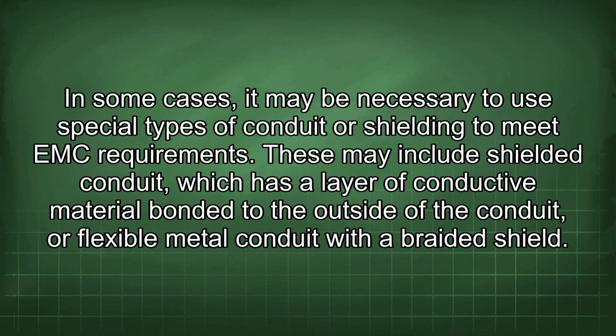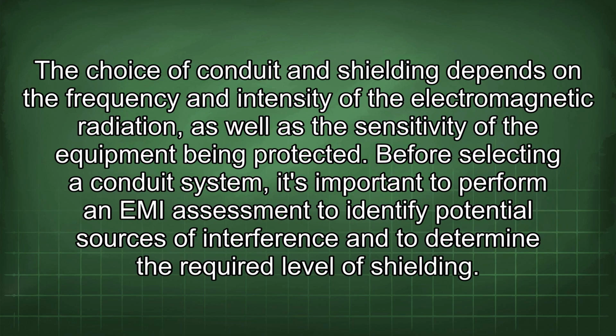In some cases, it may be necessary to use special types of conduit or shielding to meet EMC requirements. These may include shielded conduit, which has a layer of conductive material bonded to the outside of the conduit, or flexible metal conduit with a braided shield. The choice of conduit and shielding depends on the frequency and intensity of the electromagnetic radiation, as well as the sensitivity of the equipment being protected.